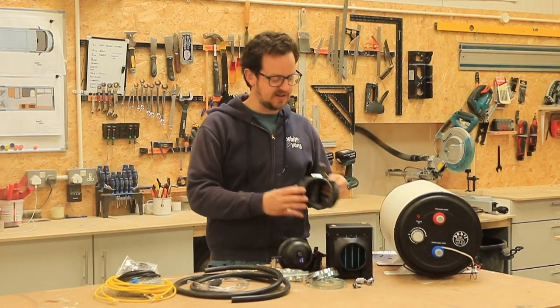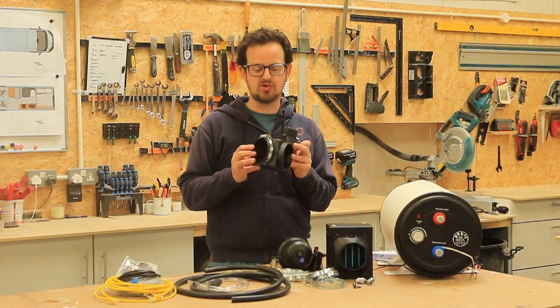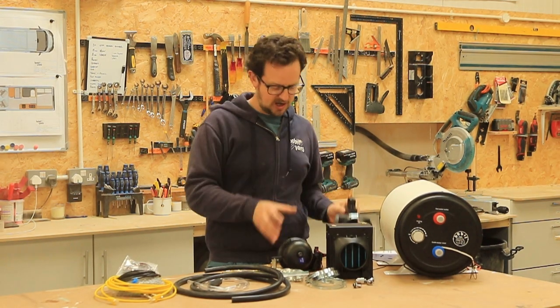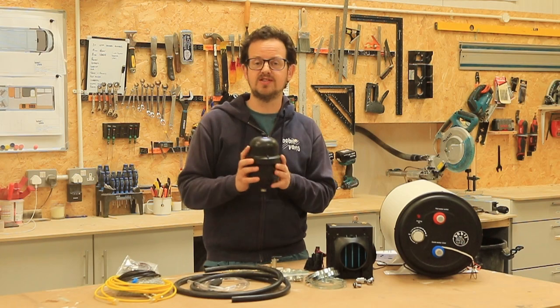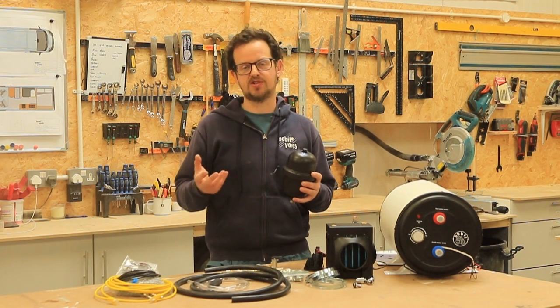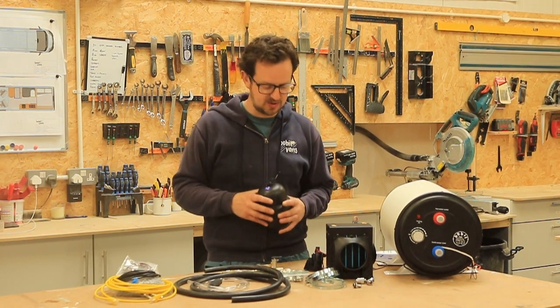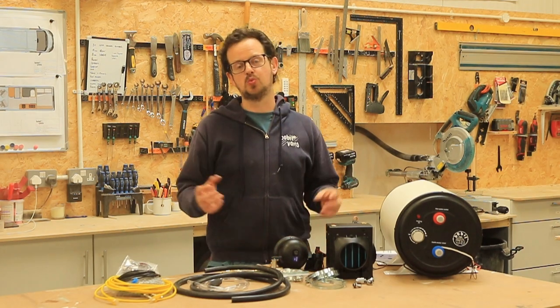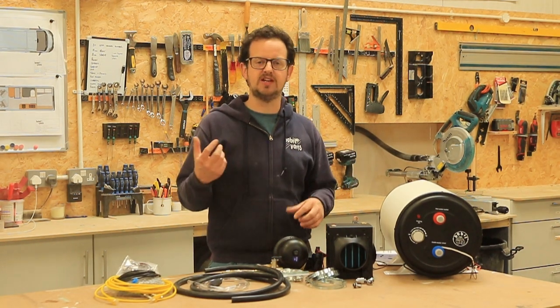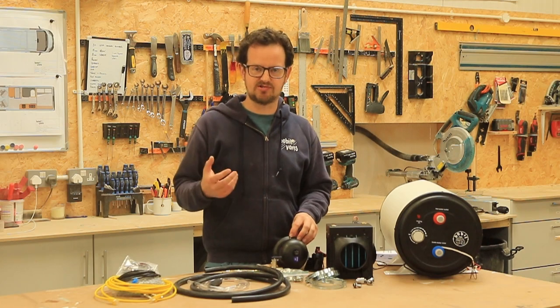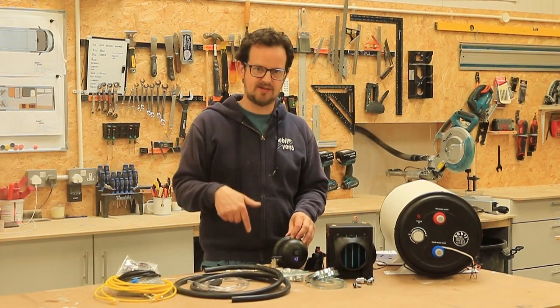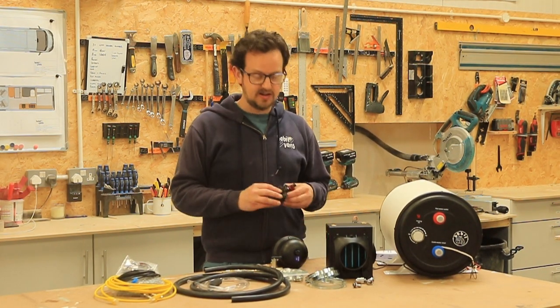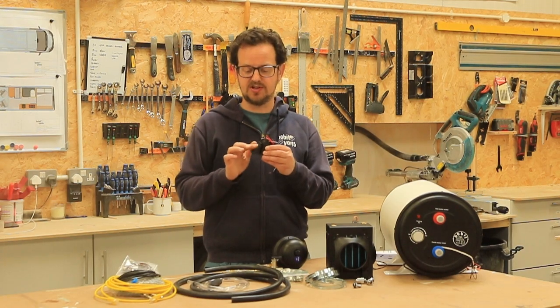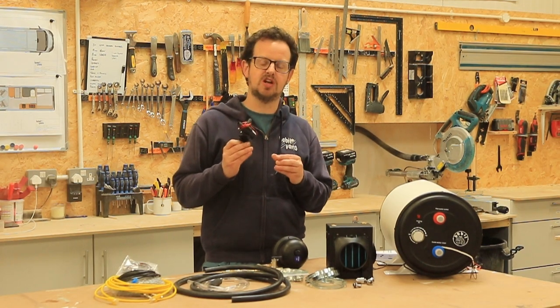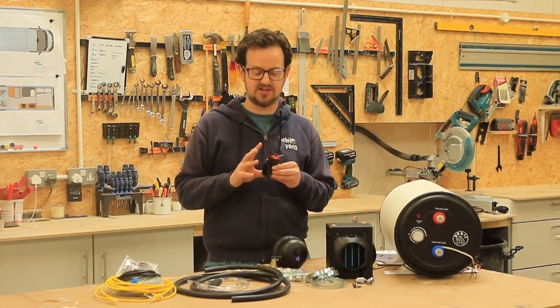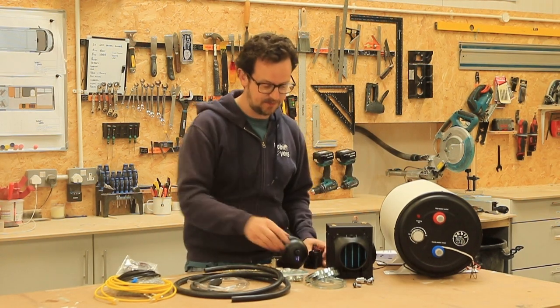We've got our automated diverter, which has got this little motor on it that moves the flap back and forth. We've now got an expansion tank in the system, which is what stops the overpressure valve from dripping out when you're heating the water. It also means that as the water cools, it doesn't cause the pump to come back on again and repressurize the system to replace the water that's leaked out, which is really great. Same little circulation pump comes on this anti-vibration bracket just to keep this really quiet, so when this is in use you can barely even hear it.